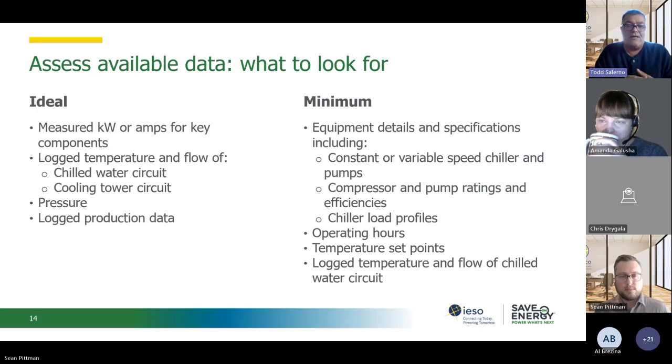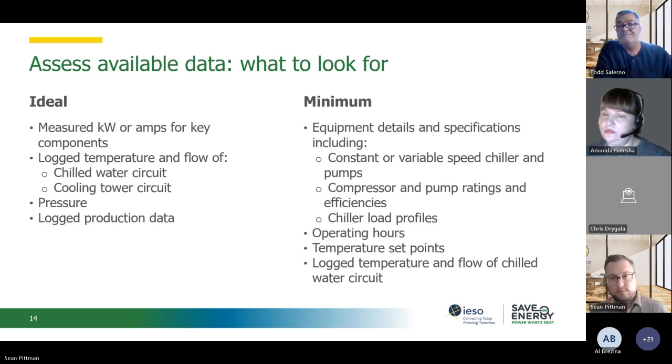Another one I've found very useful is going through the chiller logbook. Most of the larger chiller plants, and especially process refrigeration plants, have to have a logbook, and they can give you a lot of information on pressures and temperatures as well. Yeah, it's a very good point. Noting valve positioning, absolutely.